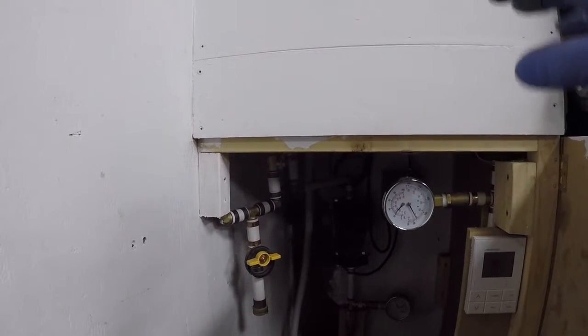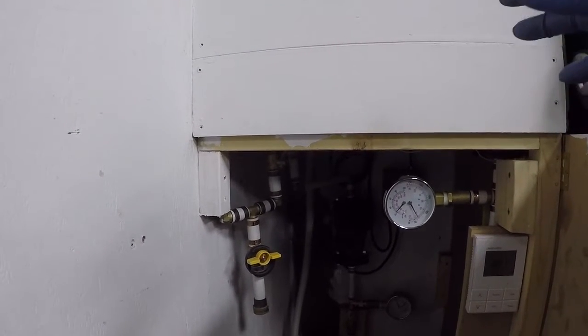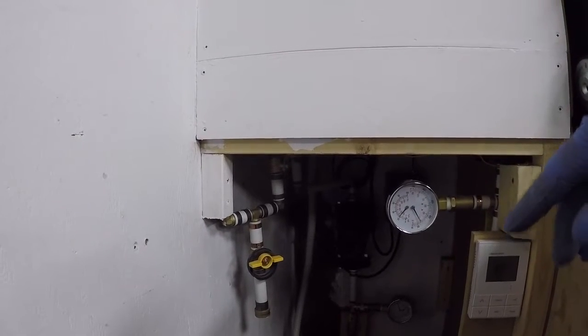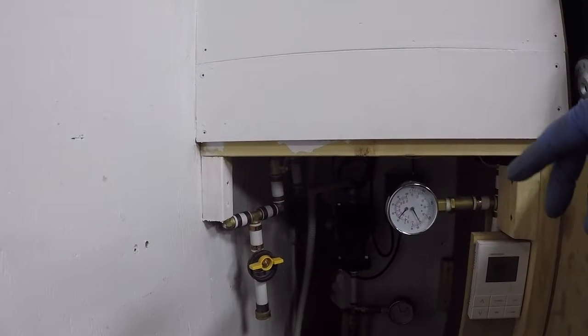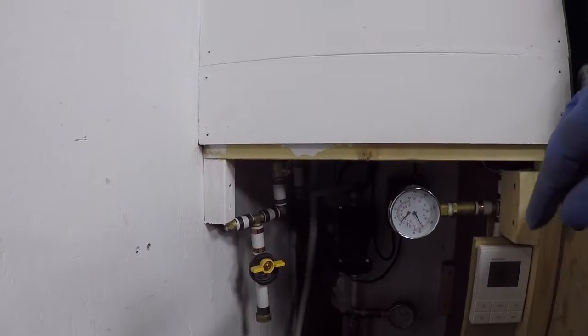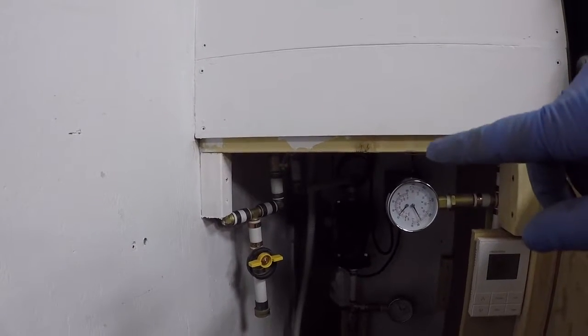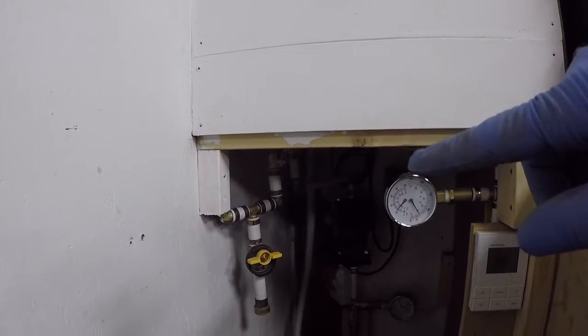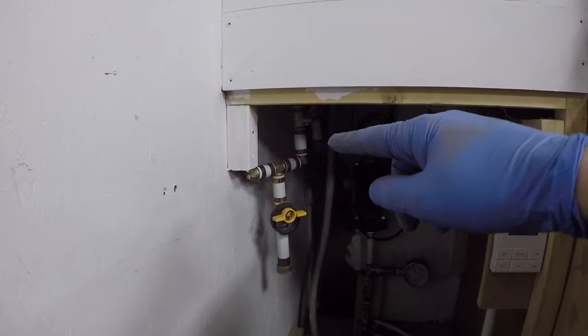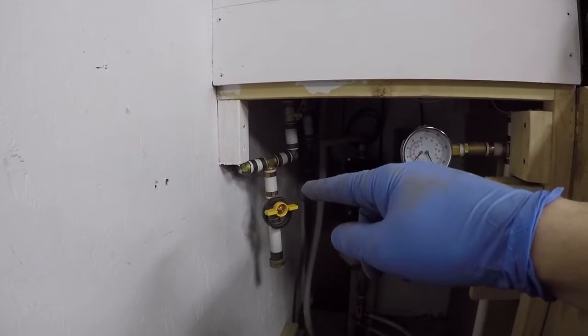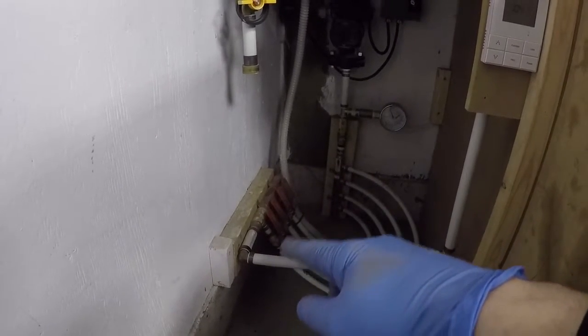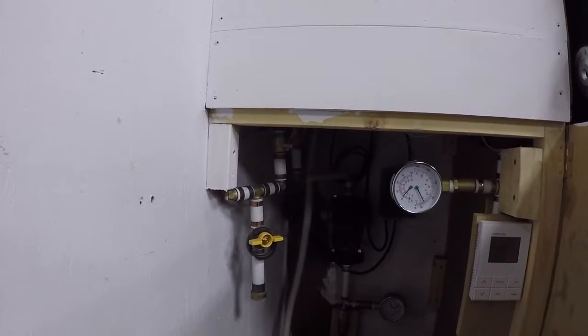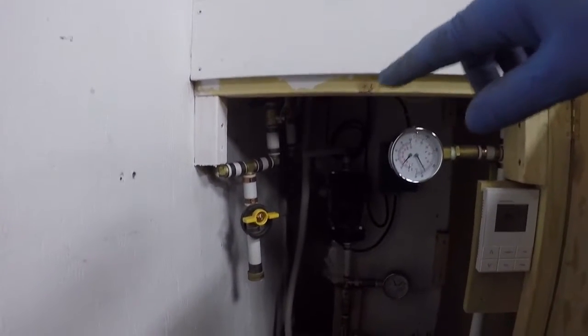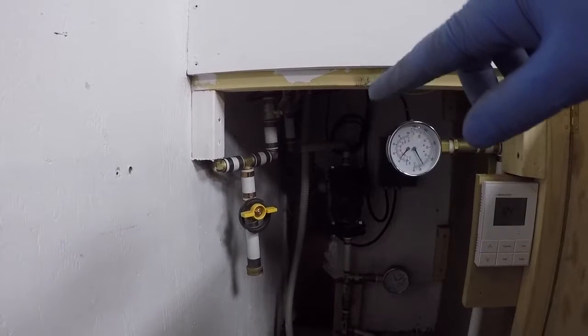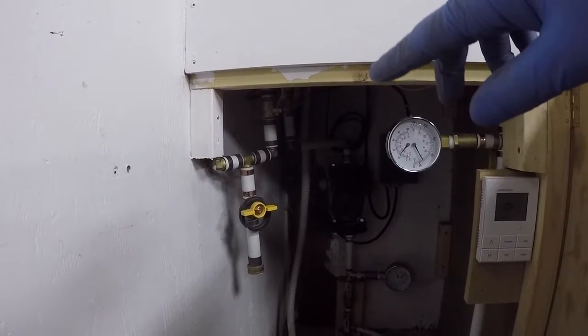Because this system is custom built, I didn't have the same kind of space restrictions or design constraints that the average person may have. So the way that I designed this was, instead of coming out of the water heater and going down into the floor, you see it would have been very easy for me to come out of the bottom of the water heater and just go straight down into that manifold. The problem with that is that if you're going to get air, it is most likely going to be after the water is heated. So the hotter water is going to tend to form bubbles in it.